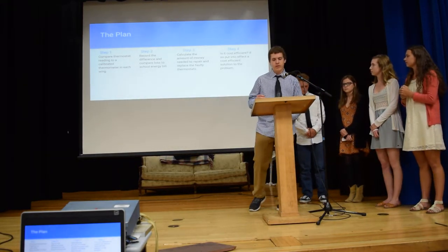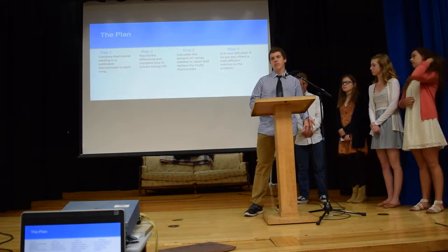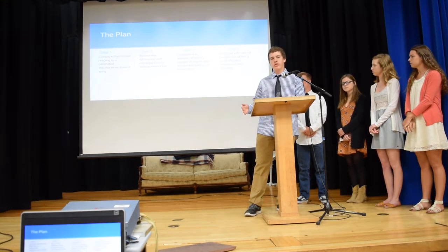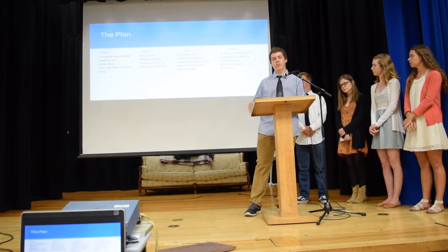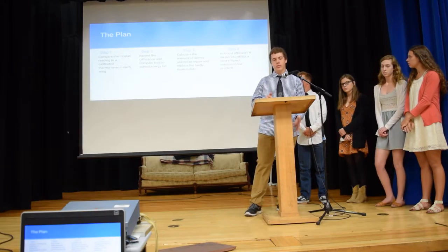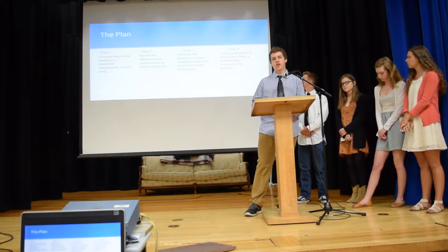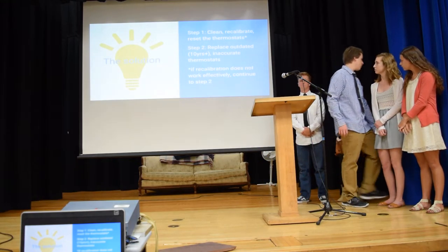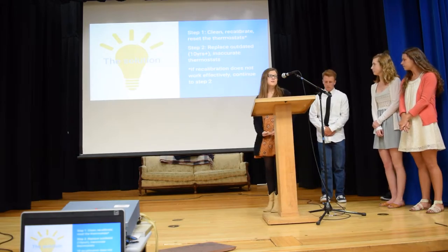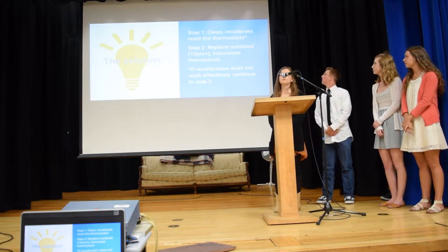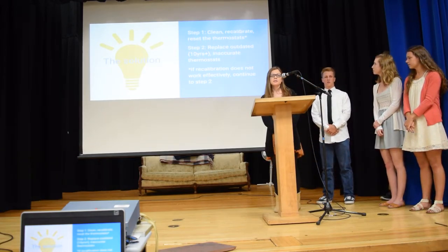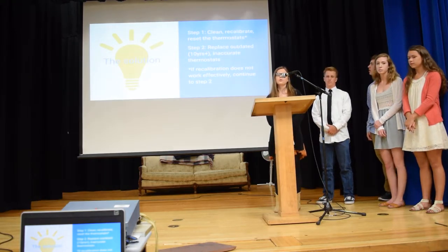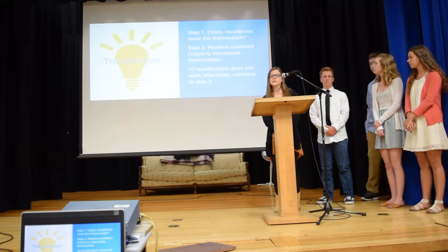Our plan was to find how much energy and money was being lost and wasted, then find how to either recalibrate the thermostats to improve their accuracy or replace them. To replace them, we had to see how much it would cost to replace each thermostat and determine which thermostats need replacing. Our first step would be to recalibrate and clean the thermostats, but due to the age of some — over 10 years old — they would possibly need to be replaced.